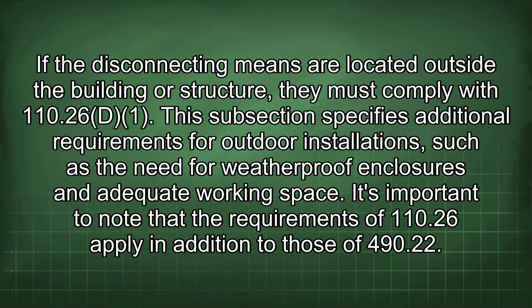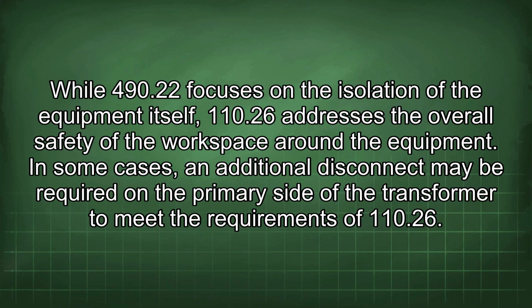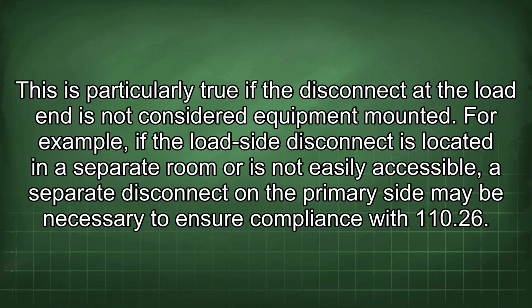It's important to note that the requirements of 110.26 apply in addition to those of 490.22. While 490.22 focuses on the isolation of the equipment itself, 110.26 addresses the overall safety of the workspace around the equipment. In some cases, an additional disconnect may be required on the primary side of the transformer to meet the requirements of 110.26. This is particularly true if the disconnect at the load end is not considered equipment mounted.